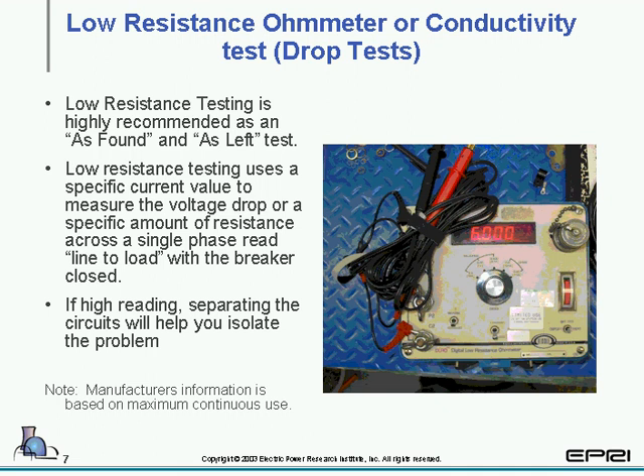Now, one of the other most common must-do tests is low resistance ohmmeter or conductivity testing. This particular test uses a specific amount, or exact amount, of current and then looks for a voltage drop and will either give its values in a resistive number or a voltage number. If you run into challenges with these not meeting the manufacturer's minimum recommendations, you can look for problems by breaking the circuit in half and then looking for whatever part of the circuit is higher than expected, or higher than if you were to look at all 3 phases, if you could find a piece of that circuit that would be higher than the other 2.